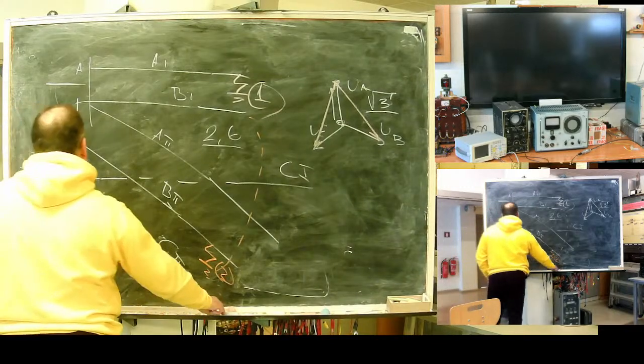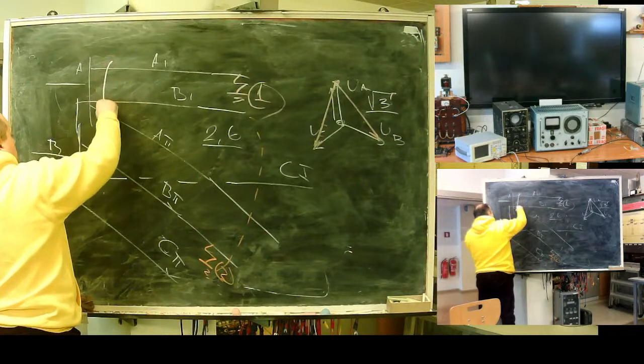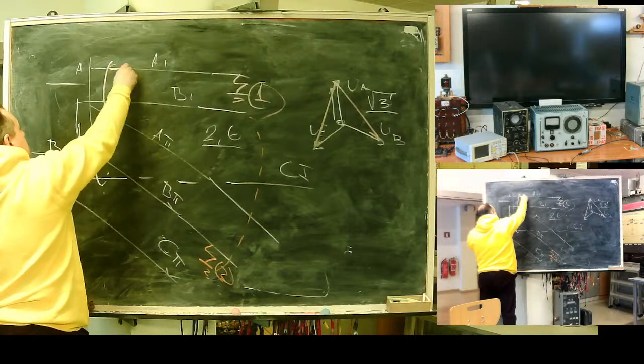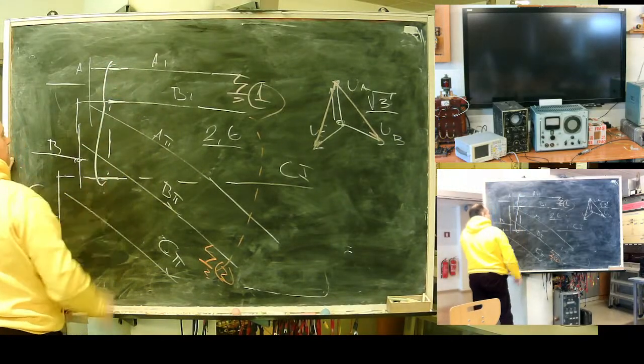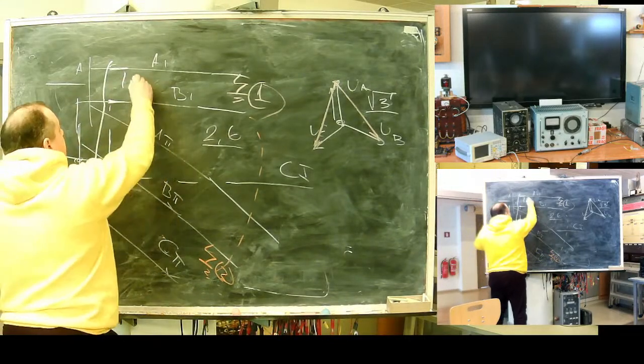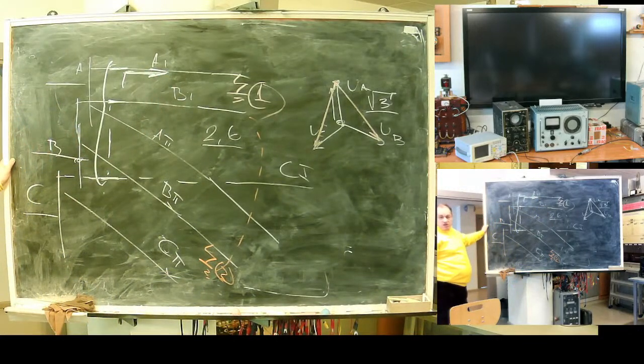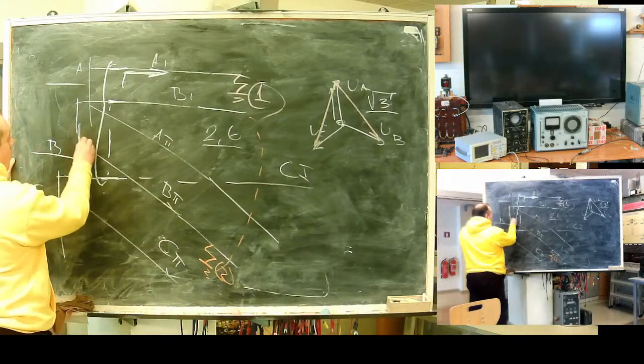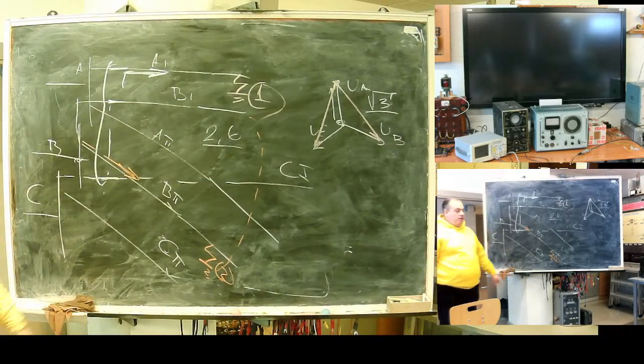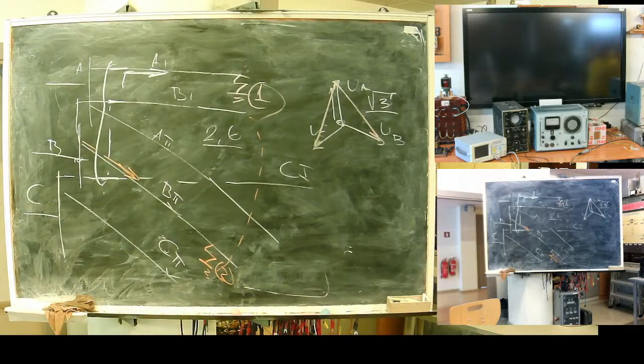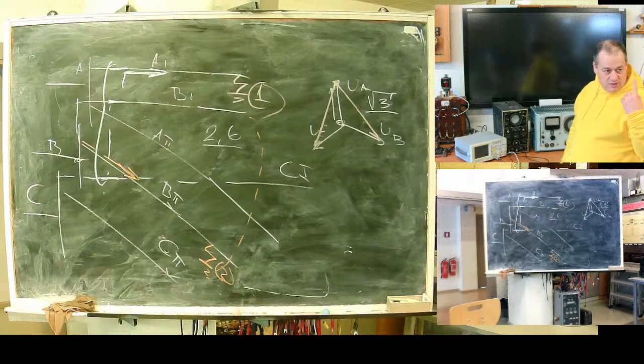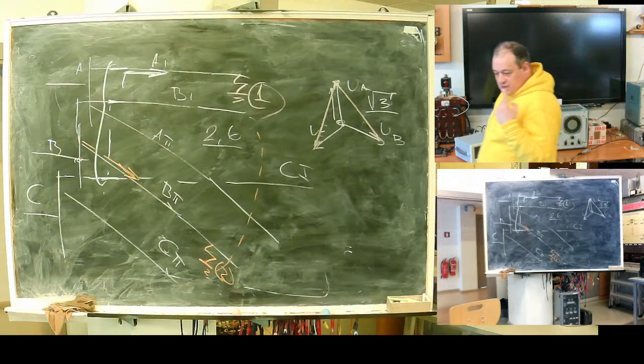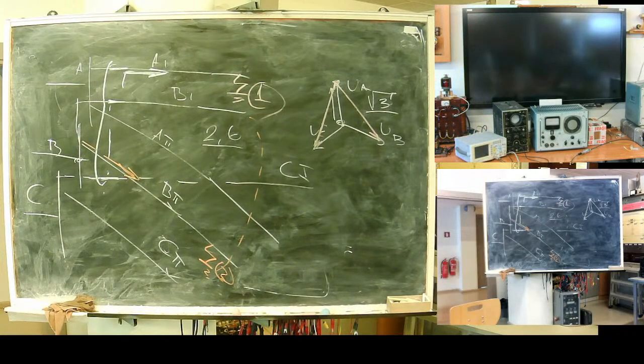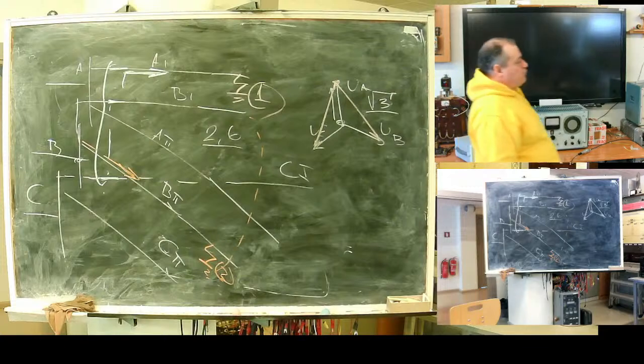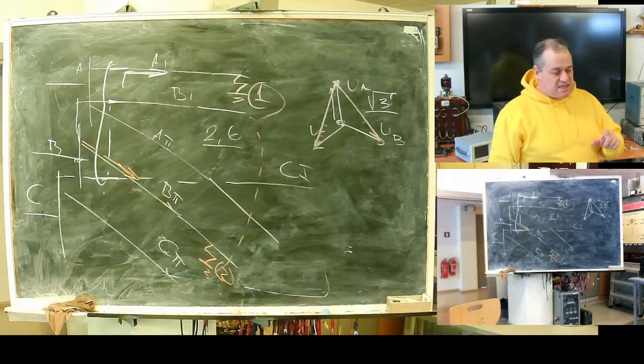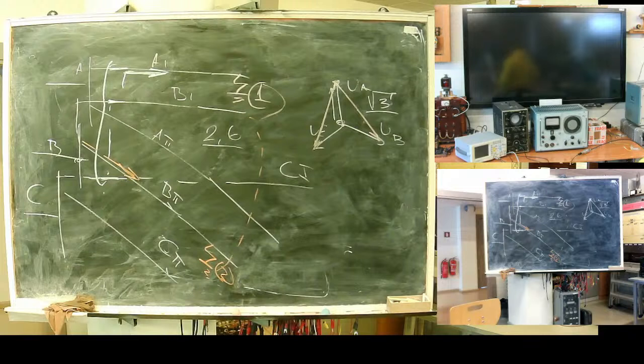But what will your protection see? Watch here, here and here. For protection number 1, only this current will be visible, and for protection number 2, only this one. A double earth fault will appear to your protections as two single line faults. Zero sequence voltage will disappear, but it will not save you. Problem: in a normal earth fault you have quite small currents, so you need something quite sensitive on these terminals.